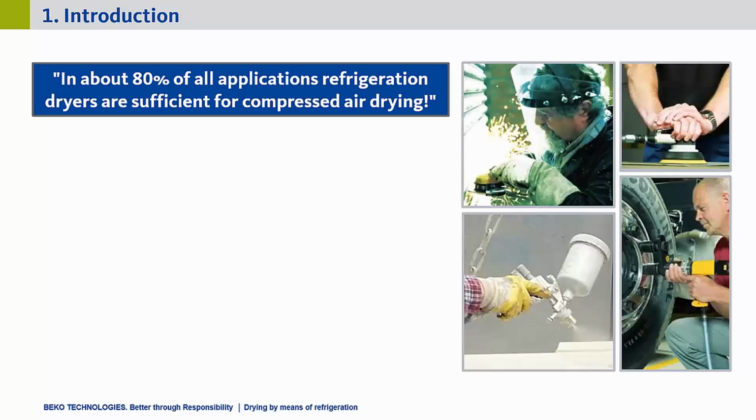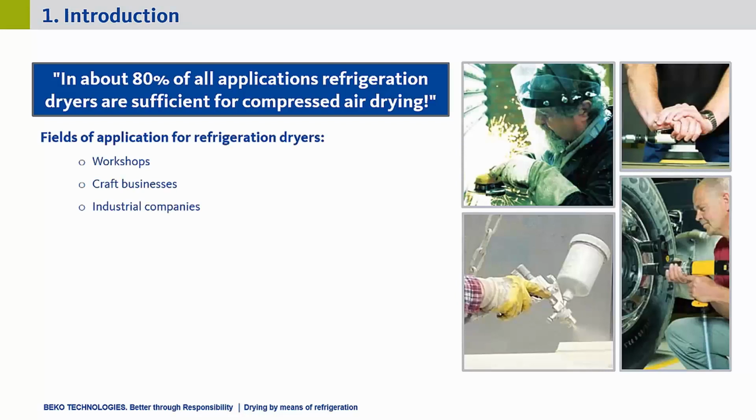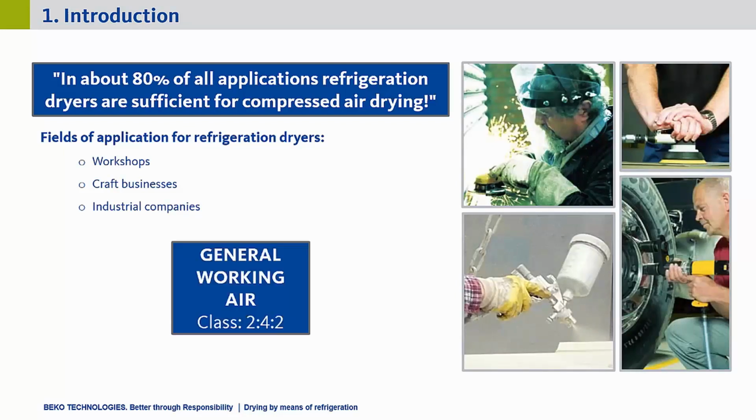So in the end, the refrigeration dryer fits into almost all workshops, also into craft businesses and industrial companies, as the most basic form of general treatment or pre-drying, simply everywhere where the quality class 242, also called general working air, is sufficient for the application. And with that, we are already through with our little introduction and comparison.